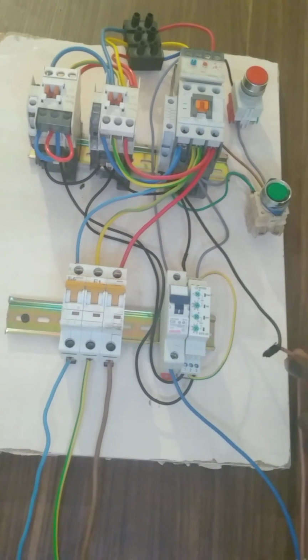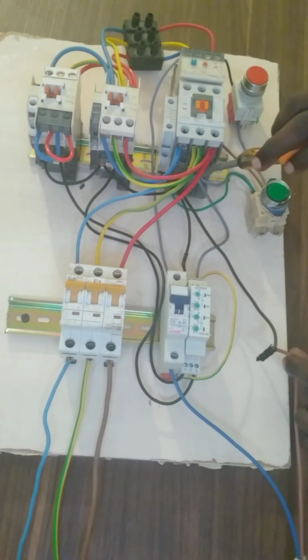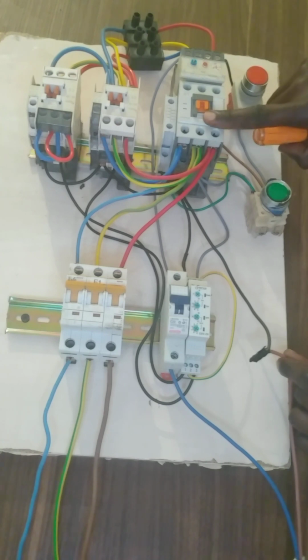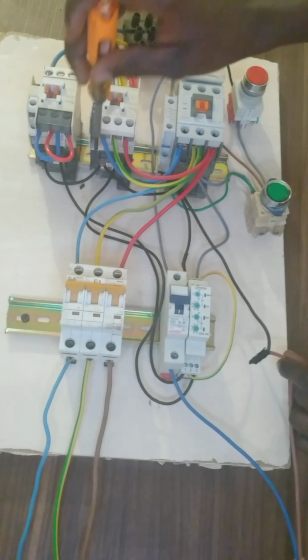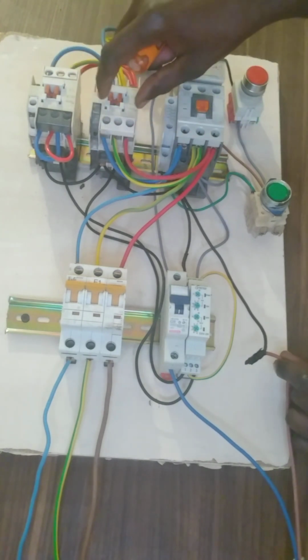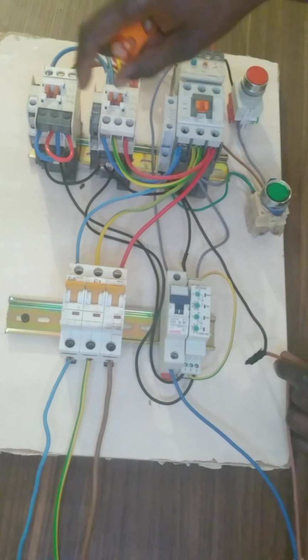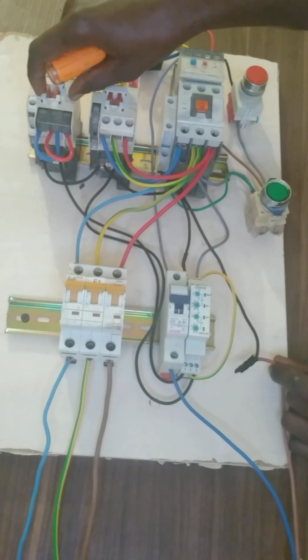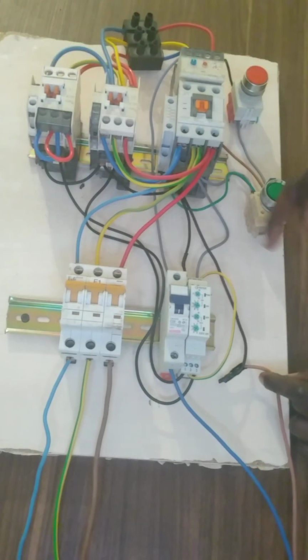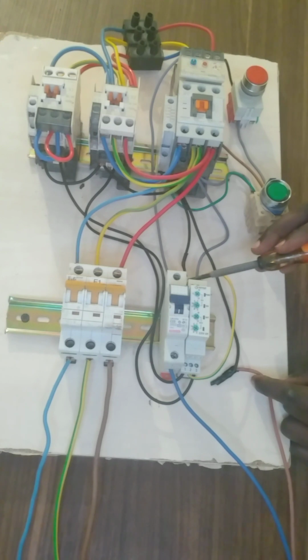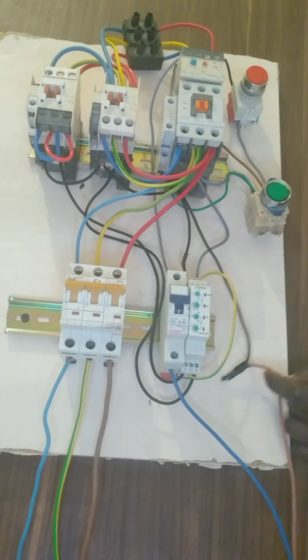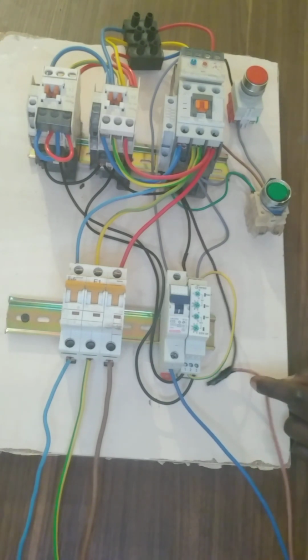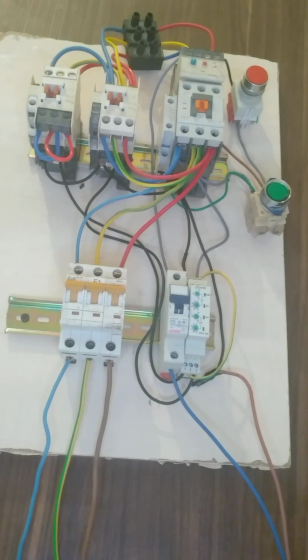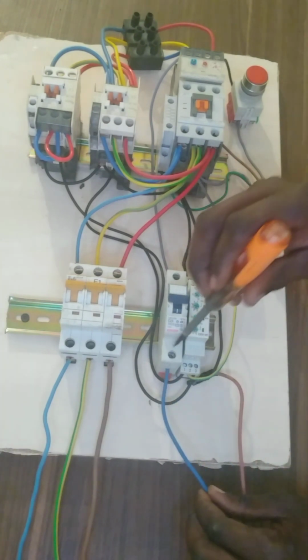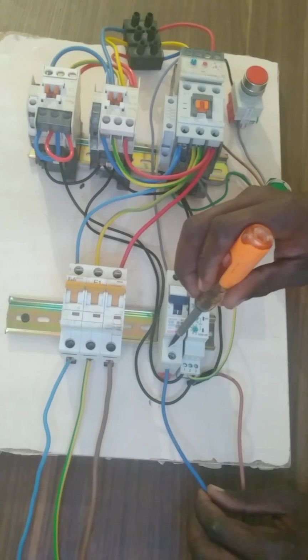Neutral is going directly to the A2 of the main contactor, then I take a branch to the A2 of the delta contactor. Also I connected to the A2 of the star contactor, and also to the A2 of the timer. Then I finish the neutral. The line enters the circuit breaker.